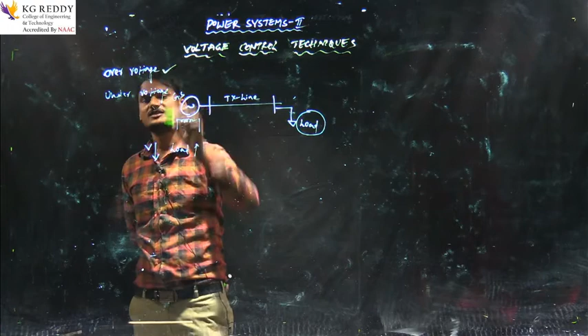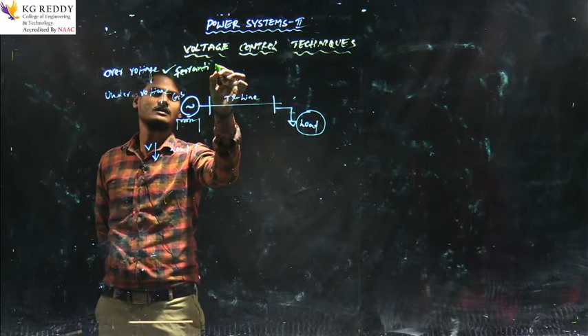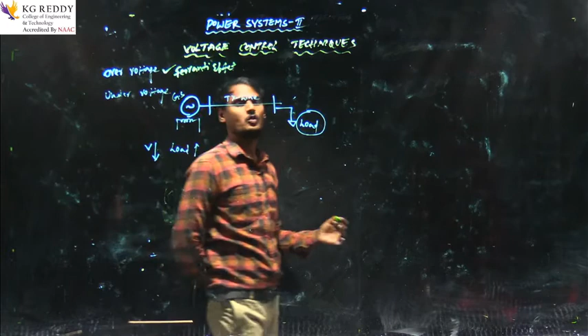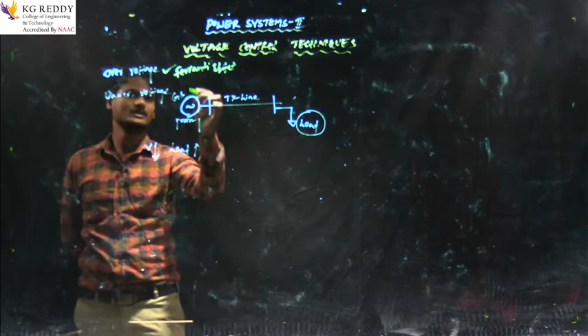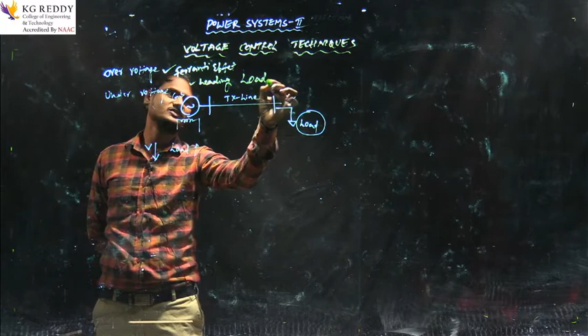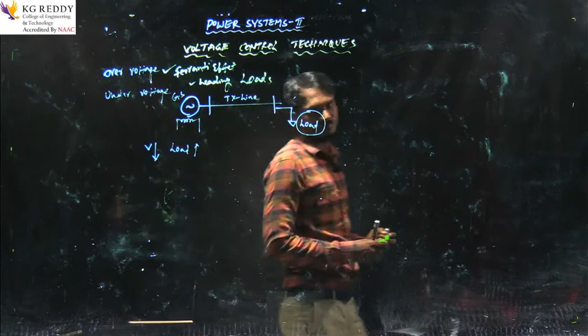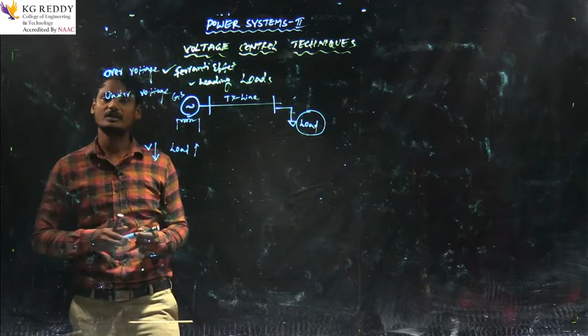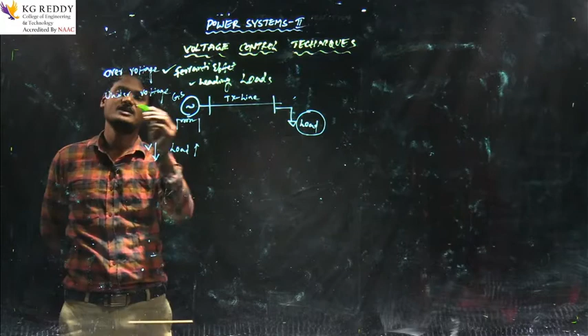Basically, over voltages occur in the transmission line due to the Ferranti effect. What is the Ferranti effect? The receiving end voltage is more than the sending end voltage. Another reason is leading loads. Because of these two things, over voltage may occur in the transmission line, right? Another thing is under voltage. We get this type of under voltage condition because of lagging load conditions.